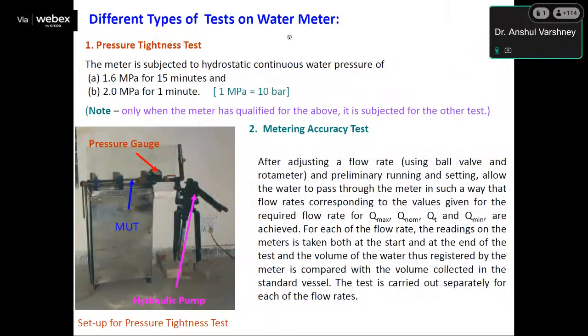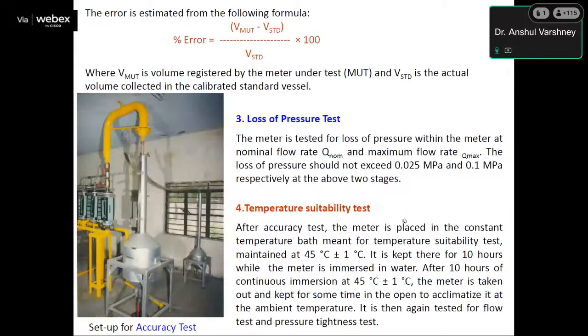Different types of tests are performed on the water meter testing facility, like the pressure tightness test. The meter is subjected to hydrostatic continuous water pressure of 1.6 megapascal for 15 minutes and 2 megapascal for 1 minute. Only when the meter has qualified for the above is it subjected to other tests like the accuracy test, which is done at minimum flow, transitional flow, nominal flow, and maximum flow. Next, the loss of pressure test. The meter is tested for loss of pressure within the meter at nominal flow rate and maximum flow rate. The loss of pressure should not exceed 0.025 megapascal and 0.1 megapascal respectively at the two stages.